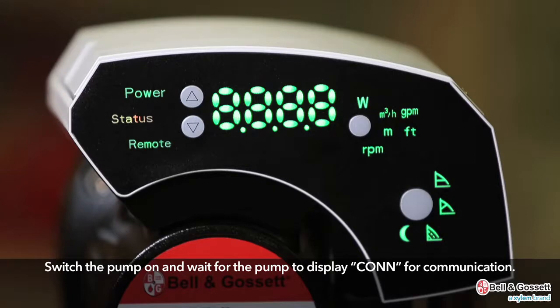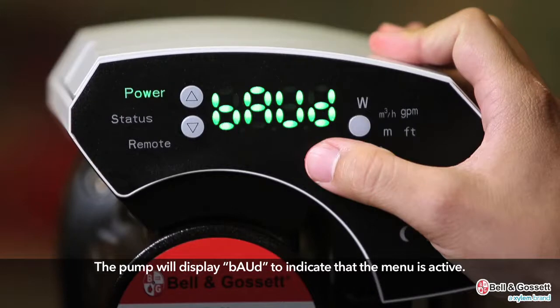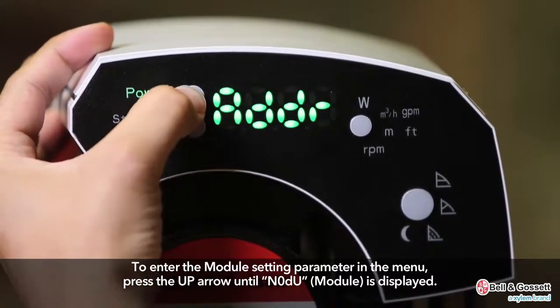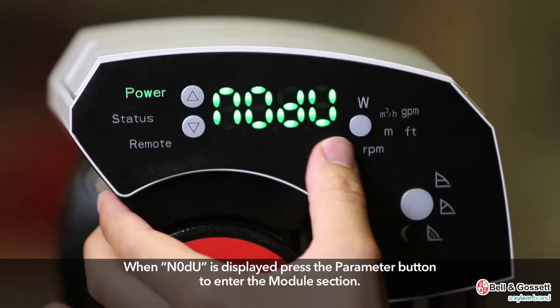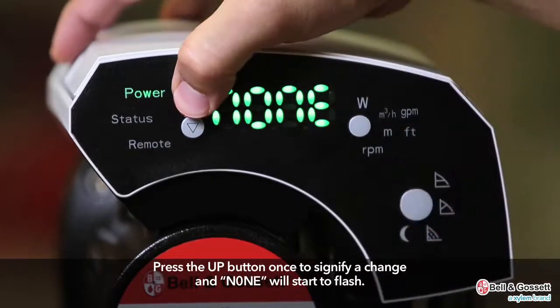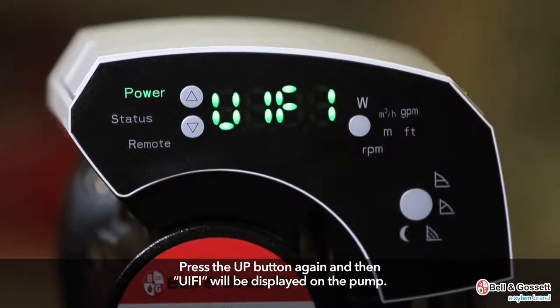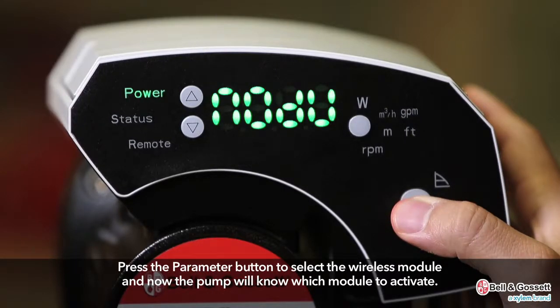Switch the pump on and wait for the pump to display CONN for communication. When CONN is displayed, press the parameter button to enter the menu. The pump will display BAUD to indicate the menu is active. Press the up arrow until NODU module is displayed, then press the parameter button to enter the module section. NONE will be displayed, meaning the pump will not activate the module connection. Press the up button once to initiate a change — NONE will start to flash. Press up again and UIFI will be displayed. Press the parameter button to select the wireless module so the pump will know which module to activate.